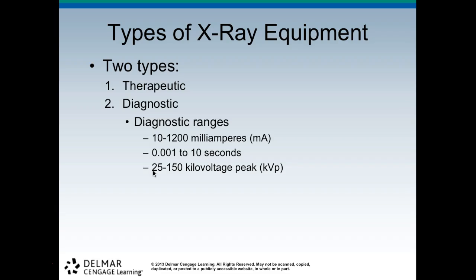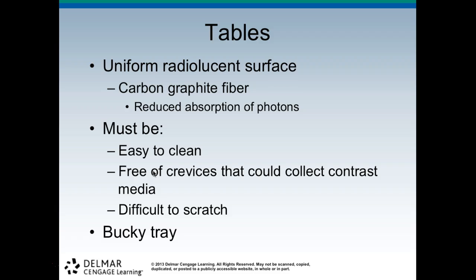All right, so basic stuff. We're going to start very basic and work our way up into more complex. So the two types of X-ray equipment are therapeutic and diagnostic, and diagnostic obviously is what we're focusing on. So we have 10 to 1200 mA, 0.001 to 10 seconds, and 25 to 150 kVp ranges. So tables. We've talked about this in the past, so they're uniform and their radiolucent surface is carbon graphite fiber, which reduces absorption of photons. So that's why we use the carbon graphite. It has to be easy to clean, free of crevices that could collect contrast, and difficult to scratch. They also have to have a Bucky tray, or if you guys are completely digital, a digital receptor underneath.